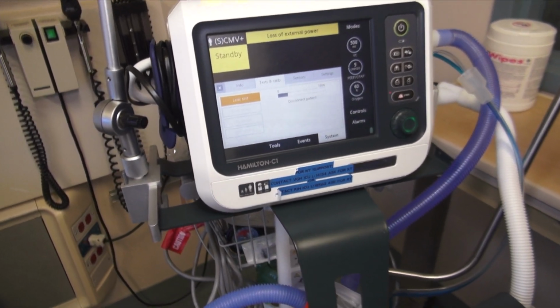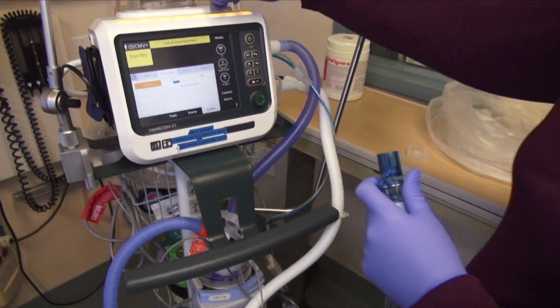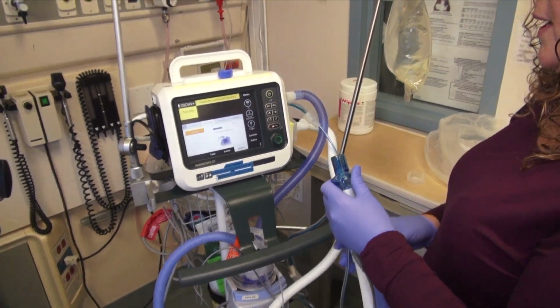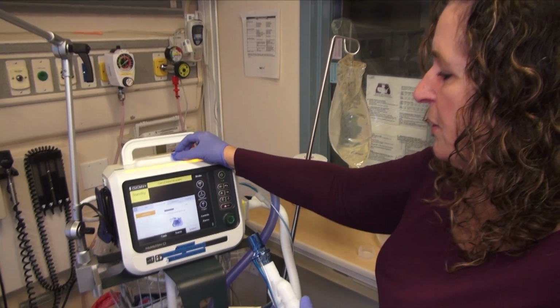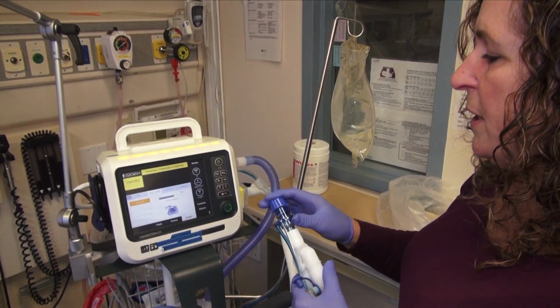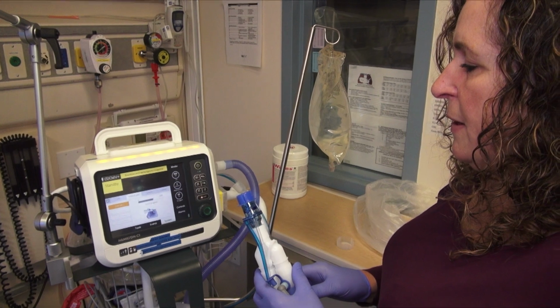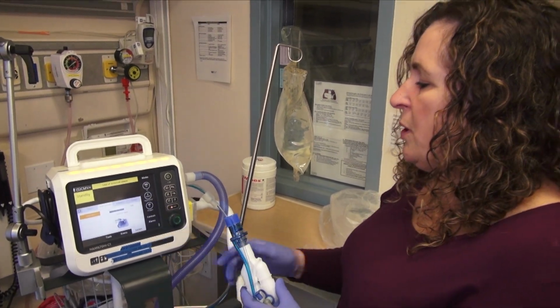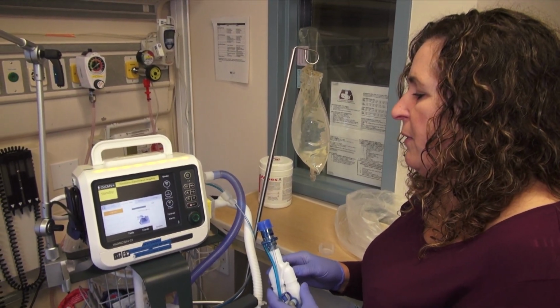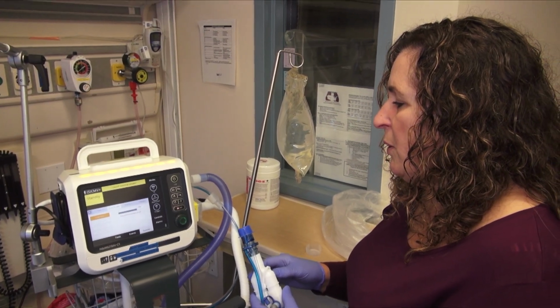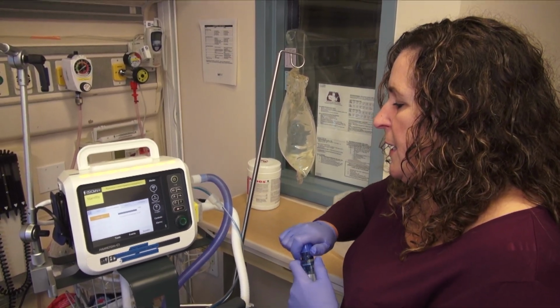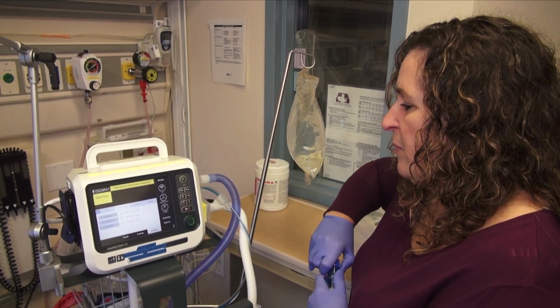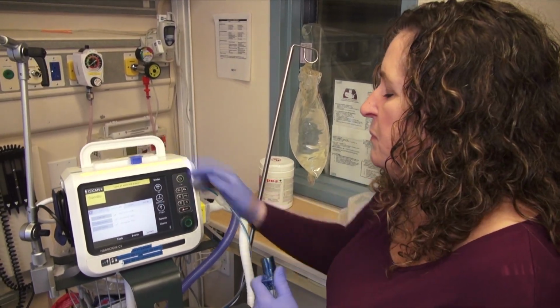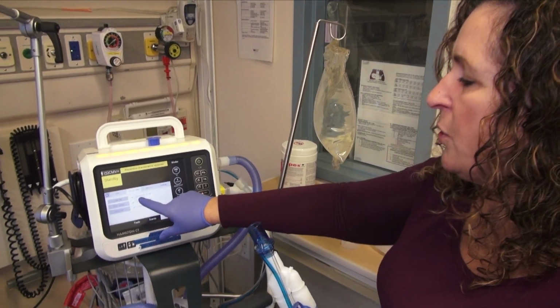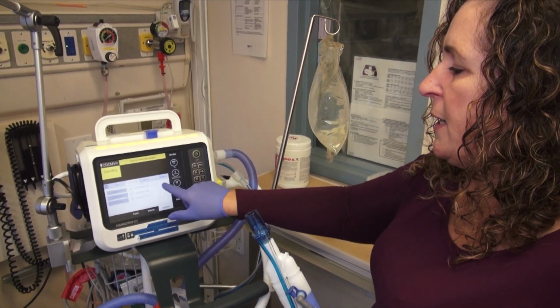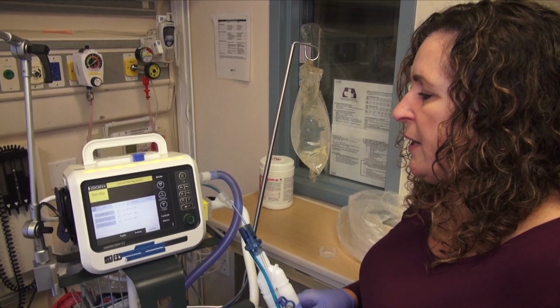So it's saying disconnect the patient. We are going to take the blue piece off and just put it up, and it's saying block the circuit. This is why I keep the blue piece on here, so we can keep the circuit clean. The picture will show you, guide you throughout everything that you need to know about the ventilator. So we're going to reconnect. In this case, just open up the circuit again.